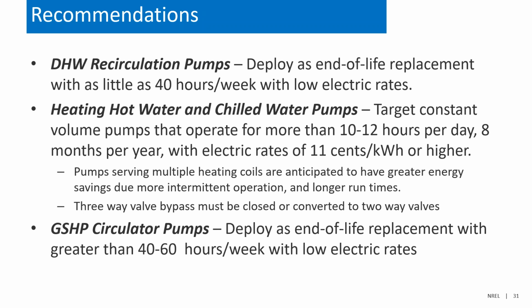Something else to keep in mind with these is a lot of times, like with radiant heating coils or even with air handlers, you might have one pump that serves multiple coils instead of the case that we had where it's one pump per one coil. In those cases, you should have better economics because those are operating continuously throughout the day. And you'll have a greater degree of variation in your load. So look for those radiant baseboard heating opportunities.